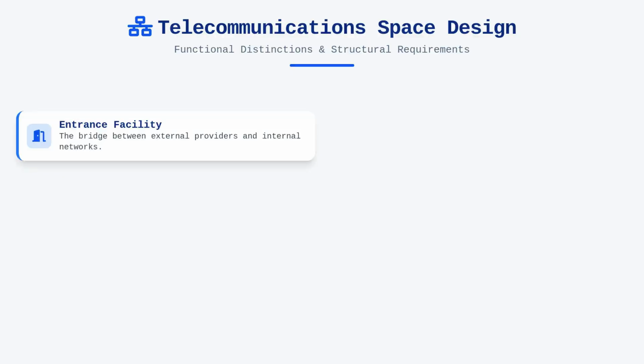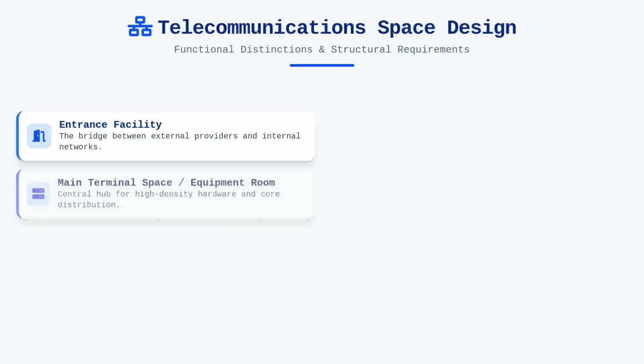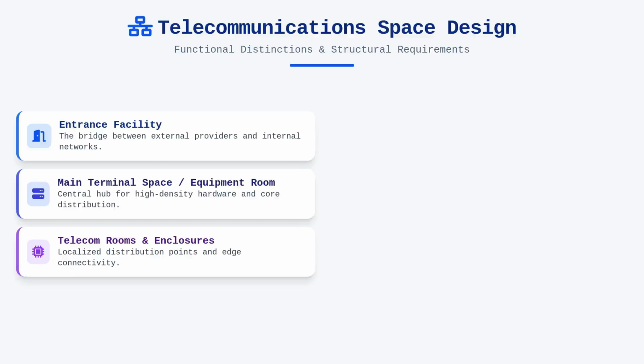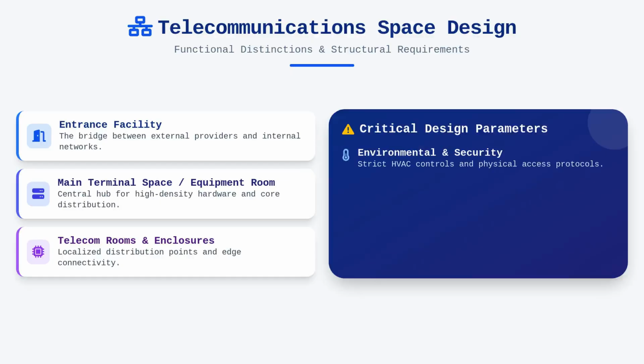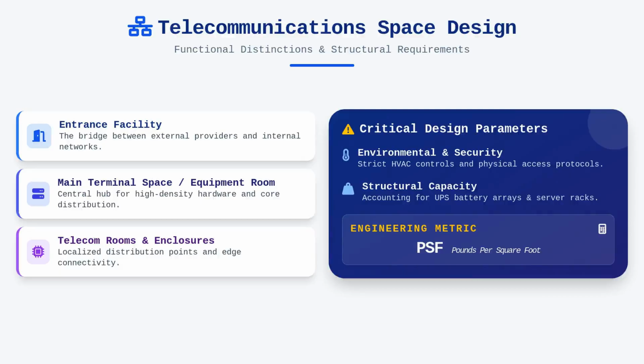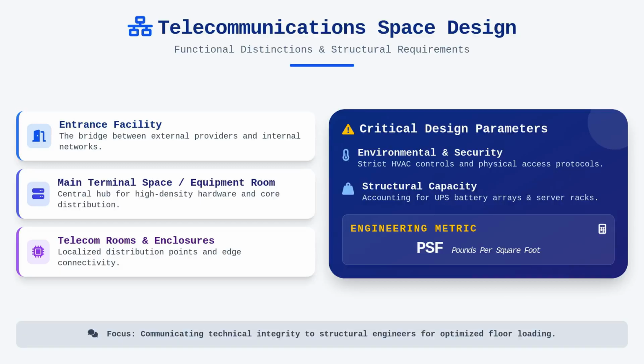Understanding the functional distinctions between various telecommunications spaces is the bedrock of our design methodology. We will define and contrast the specific roles of the entrance facility, the main terminal space, the equipment room, and the various telecommunications rooms and enclosures. Each of these spaces carries unique requirements for environmental control, physical security, and structural capacity that you must articulate clearly to the design team. We are going to look closely at floor loading capacities, ensuring your designs account for the substantial weight of UPS battery arrays and high-density server racks. You will learn how to communicate these technical needs in terms that structural engineers respect, specifically focusing on pounds per square foot ratings and floor structural integrity.